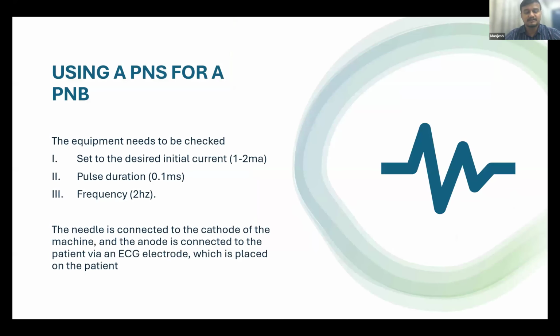So coming to using a peripheral nerve stimulator for a peripheral nerve block, the equipment needs to be checked, and it is set at a desired initial current of 1 to 2 milliamperes with a pulse duration of 0.1 milliseconds and a frequency of 2 hertz.